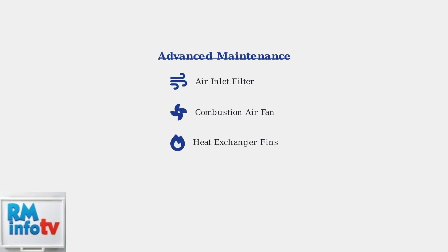For advanced troubleshooting, clean additional components including the air inlet filter, combustion air fan, and heat exchanger fins. These components affect airflow and combustion efficiency.